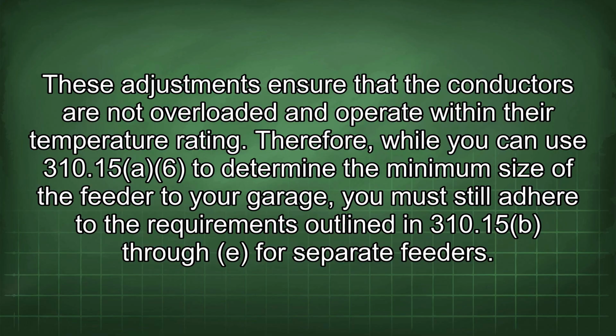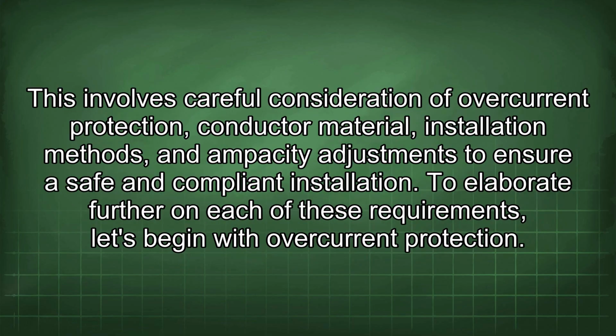Therefore, while you can use 310.15(a)(6) to determine the minimum size of the feeder to your garage, you must still adhere to the requirements outlined in 310.15(b) through (e) for separate feeders. This involves careful consideration of overcurrent protection, conductor material, installation methods, and ampacity adjustments to ensure a safe and compliant installation. To elaborate further on each of these requirements, let's begin with overcurrent protection.